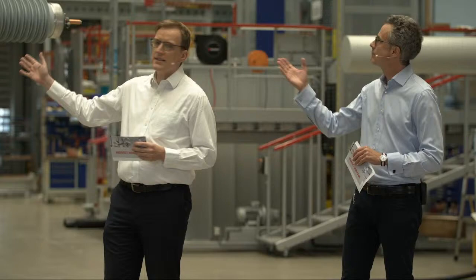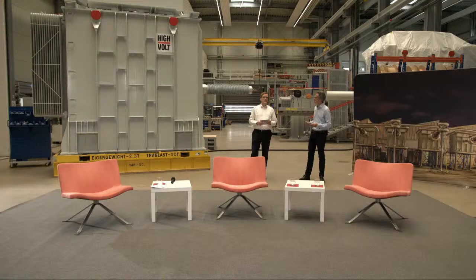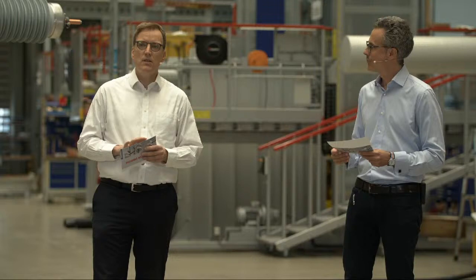On this side we can see one of the big reactors manufactured here. At the moment, six of these are under production or in final assembly. These are our XXL reactors for cable testing — 50 tons in weight, designed at a frequency of 10 Hz, with a testing power of 126 MVA.